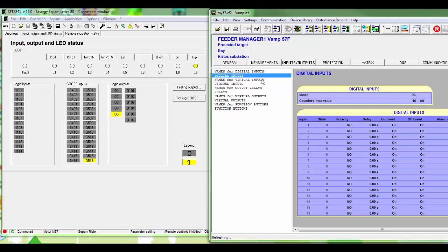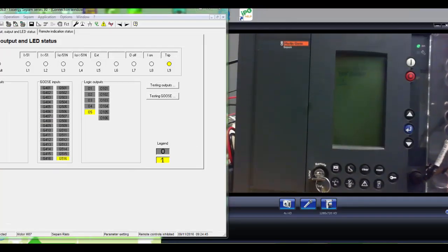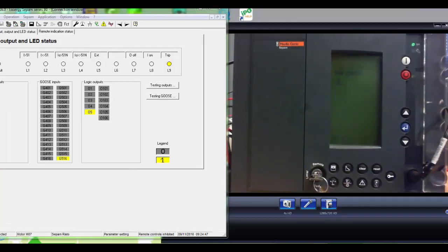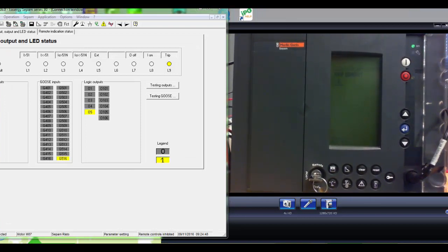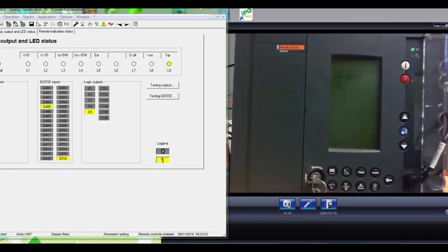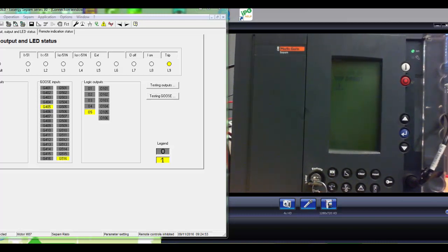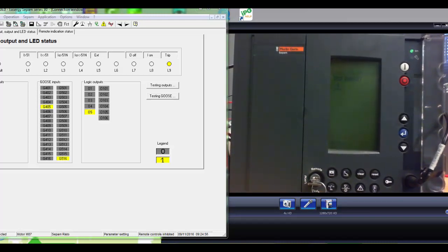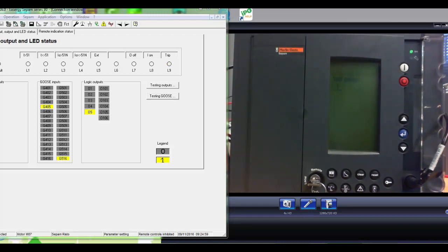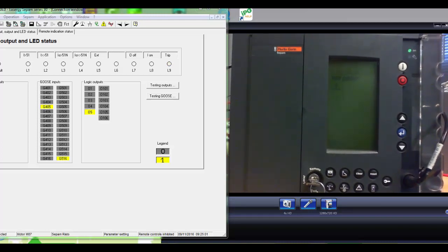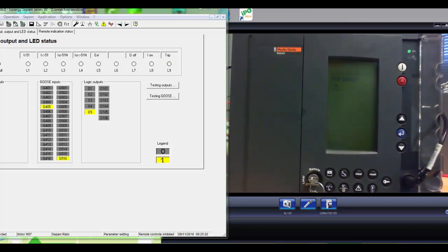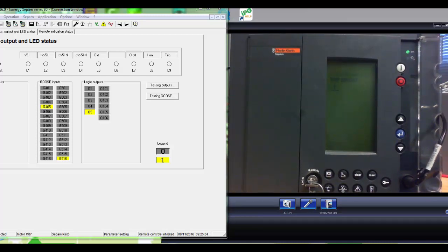Changing the status of digital input in VAMP relay will create an activation in the GOOSE signal in SEPAM. We can notice by the LED on the front that actual subscription is much faster than the SFT status update.